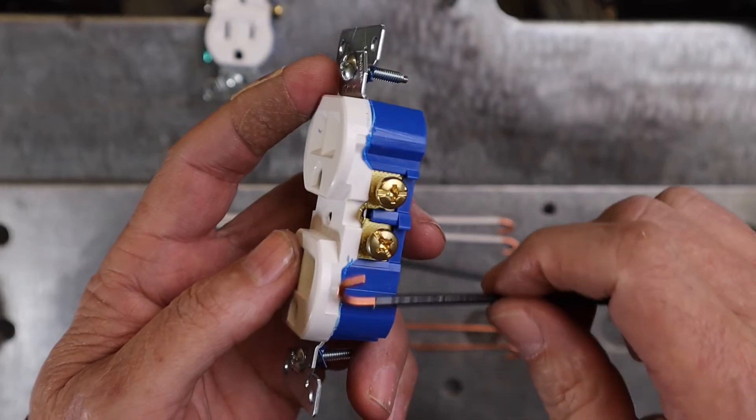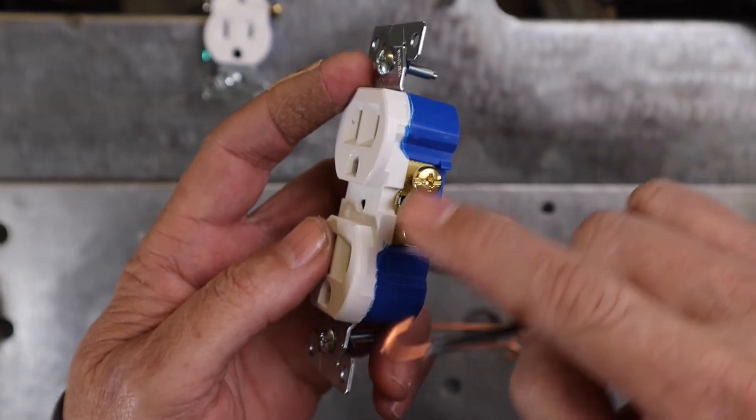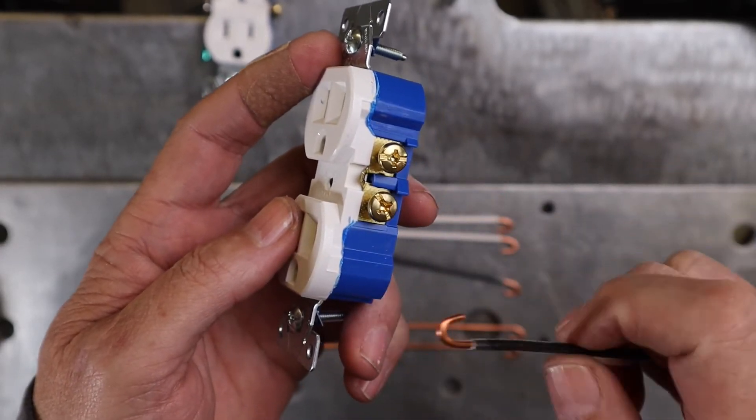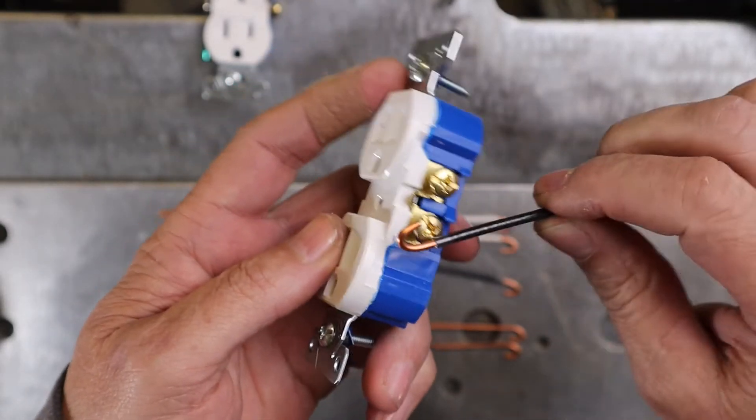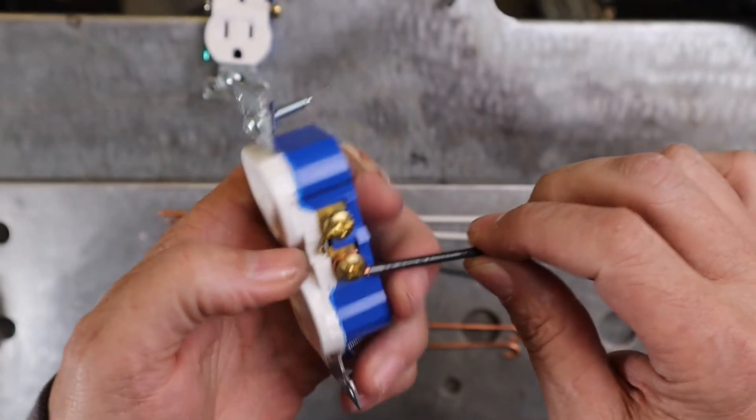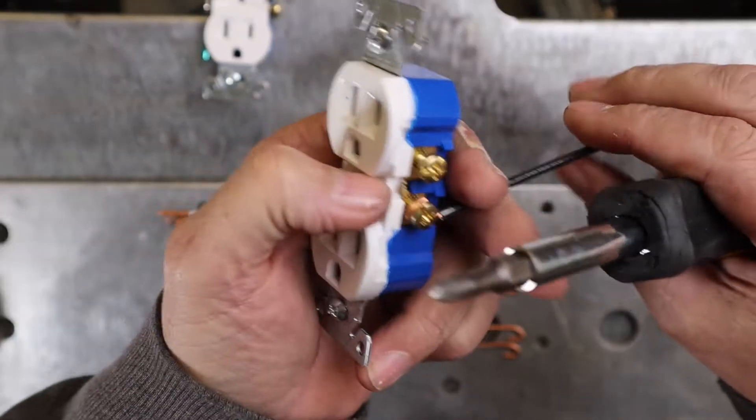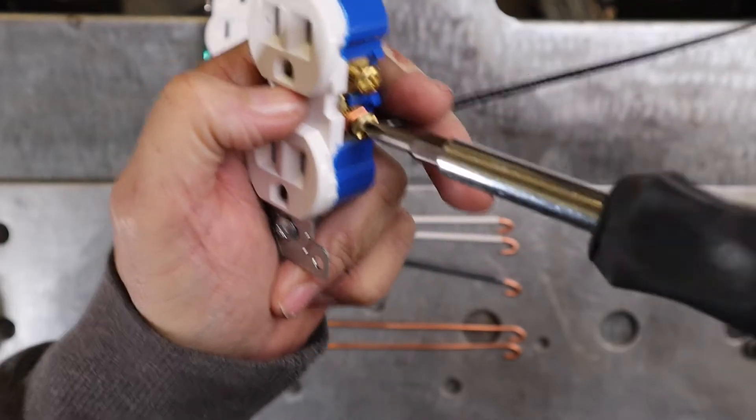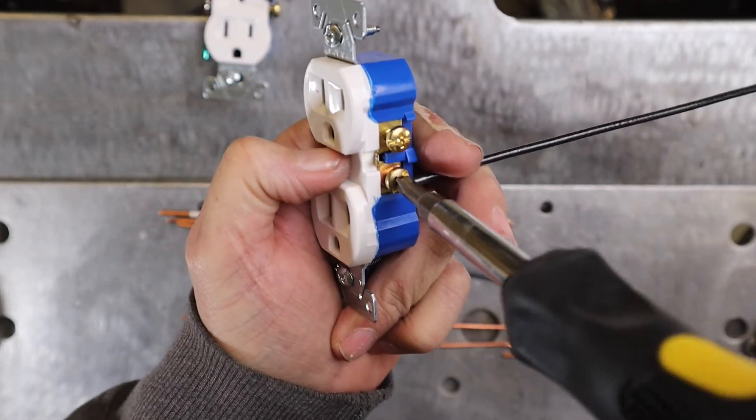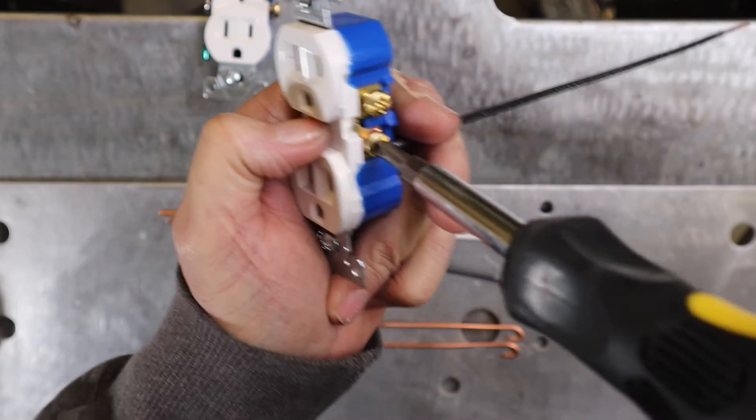Start putting your pigtails on there. Now the way this works with the pigtails, the screws are going to turn to the right to tighten, so you want that hook to be facing around to the right. So when you tighten down on the screw, it's going to try to pull the wire around the screw instead of try to push it off of the screw, if that makes sense.